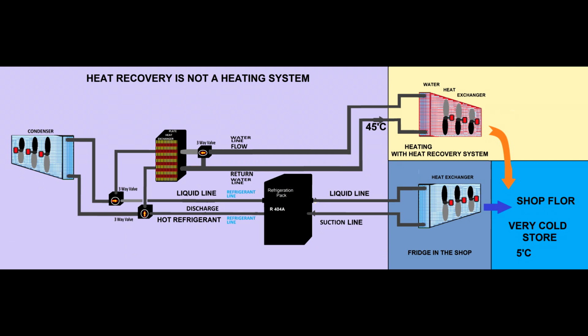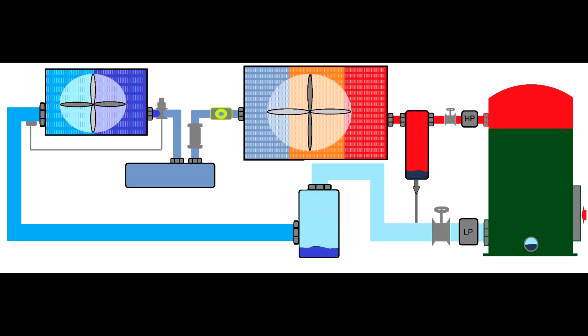Now I think you already got a glimpse of what a heat recovery is and what it is not. So as I stipulated before, if you want to recover some heat from a store, the store has to have a heating system. Now you see this is a refrigeration equipment, just a basic refrigeration equipment. So what do we do with this refrigeration equipment? Can you see the compressor head? It's red hot because that's the section where the superheated hot refrigerant goes towards the condenser. Now the condenser will eliminate that heat.